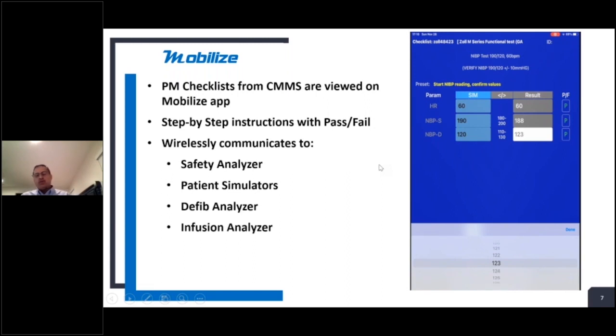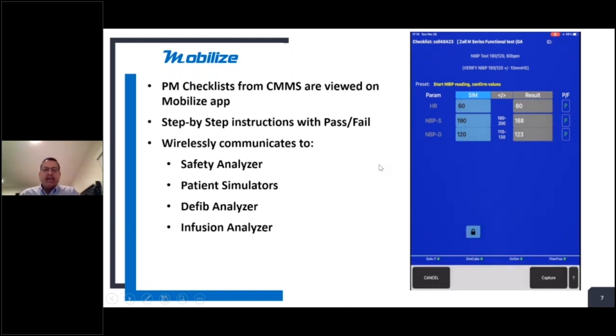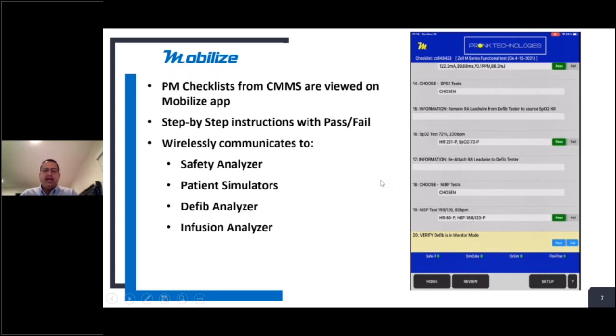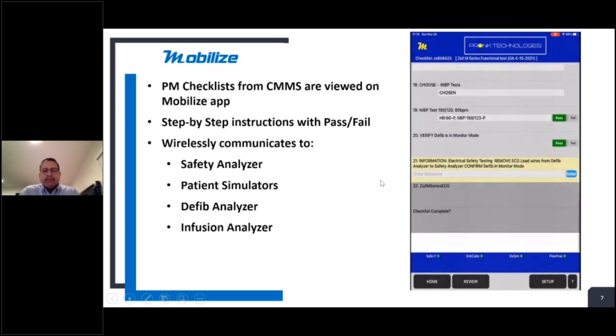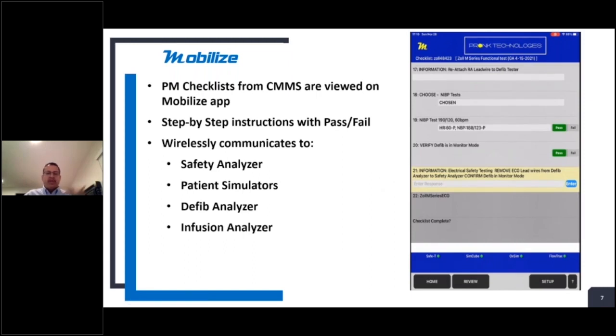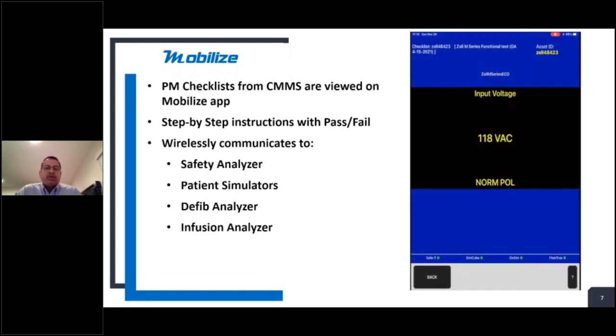So these are all user programmable. Set them up the way you would like in terms of the test points and the tolerances and the data you want to capture. So you can see here we've used a defib analyzer review simulation, and now we're going to go ahead and do the last test in this particular procedure, which is to do the safety test.